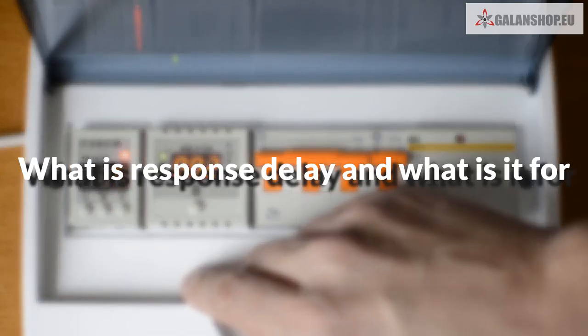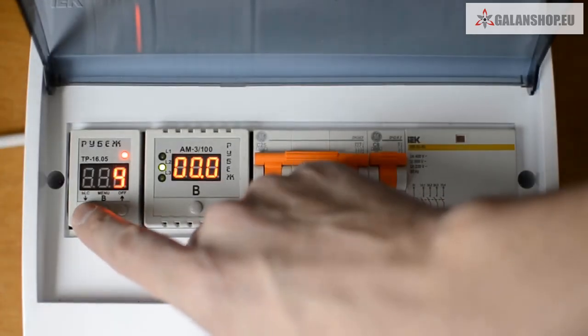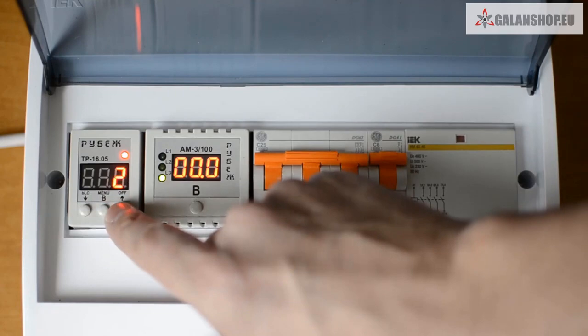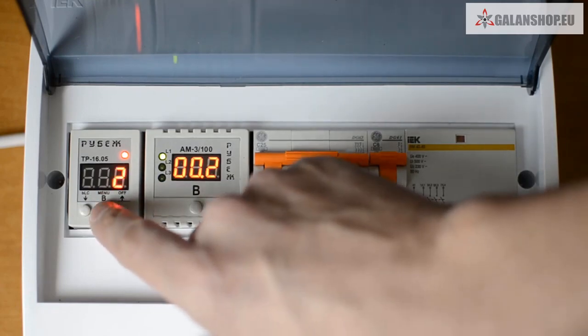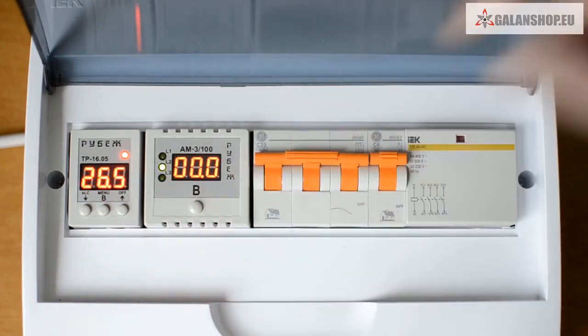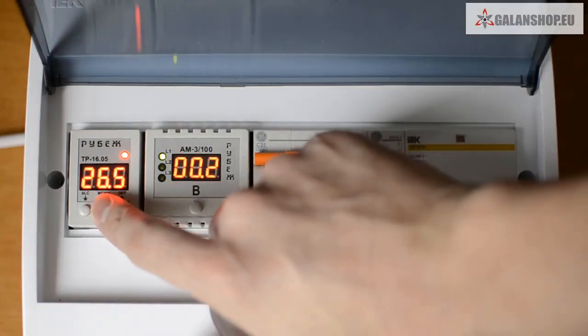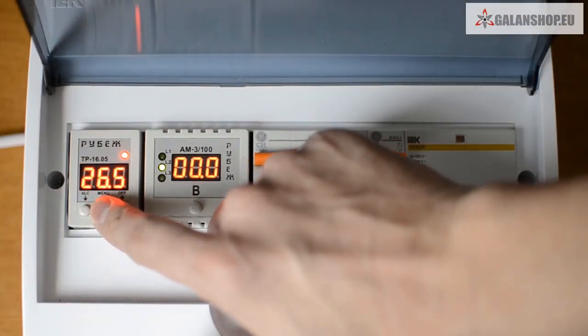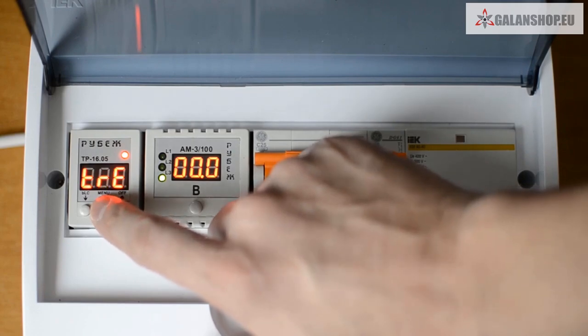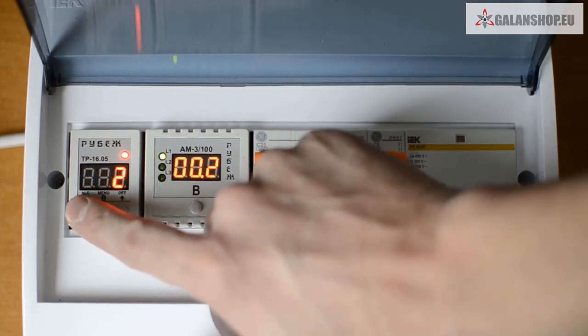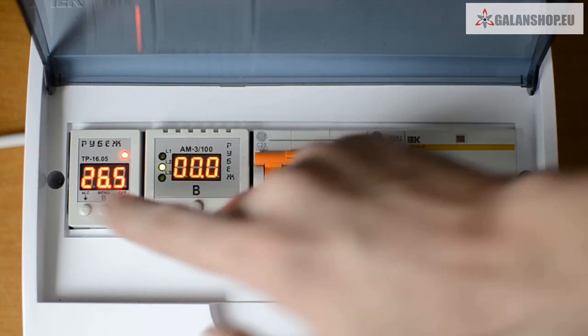What is response delay and what is it for? After the controller turns your equipment on or off, it will not respond to measured temperature changes for a required period of time, even if the temperature goes beyond the values you set. I'd like to point out that if you do not have any reason to set the response delay, it is advisable to set this value to 0. Let's set this value to 0 again, and fix it by pressing the B button.